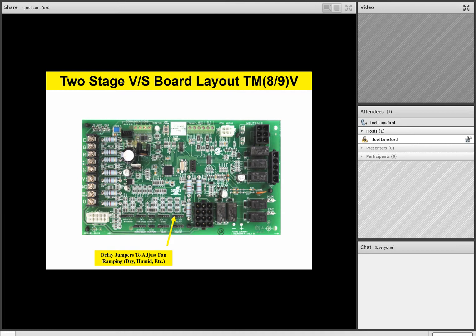The next two jumpers we're going to talk about, adjust, and again in your workbook or your handouts on page number 36, you'll look at the adjust jumper and the cool jumper. I want to stress this: the adjust and the cool jumper work together to set the control board up for the amount of airflow you need based on the size of the outdoor equipment. Let me stress that again: cool and adjust work together to set the airflow up based on the size of the outdoor equipment. Now please write this down or remember this.